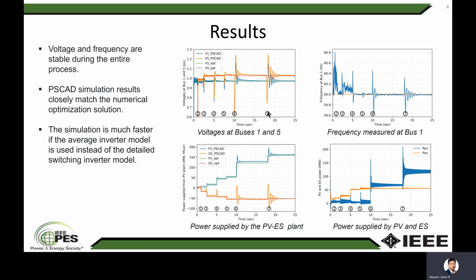This slide shows the results of the simulations. Here we have the voltage at bus 1 and bus 5. Here we have the frequency measured at bus 1. Note that bus 1 is where the PV power plant is located. And here we have the power supplied by the entire PV energy storage plant. And here we have the breakdown of power supplied by PV and by the energy storage. So during the entire simulation, you can see that the frequency and voltage magnitude are stable. There are some fluctuations following each switching event, but it becomes stable quickly after that.